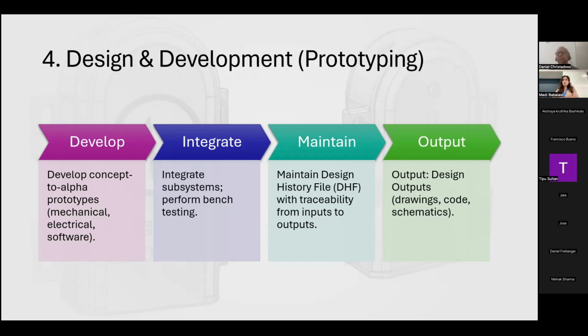So this design history file will give a complete history of the design of the whole project, so that anytime later on, if you have an issue, you can go back and say, where did we fail, or where did we do due diligence, so that you can do some root cause and correct it. So the idea of documentation, even though many times we feel the FDA or companies overdo this documentation, there is really a method to the madness. It helps you in the long run. So the design history file is a very, very important part of any medical device manufacturer and your design process. And your output, of course, of all this is your regular mechanical drawing, your schematics, your software code. At this point, these are what your design outputs are.